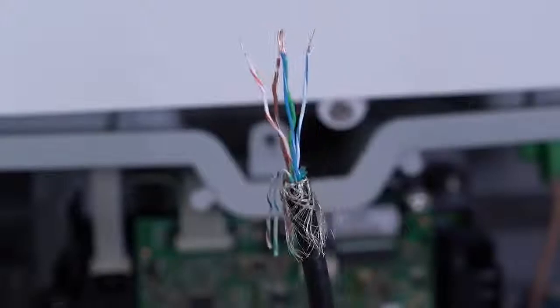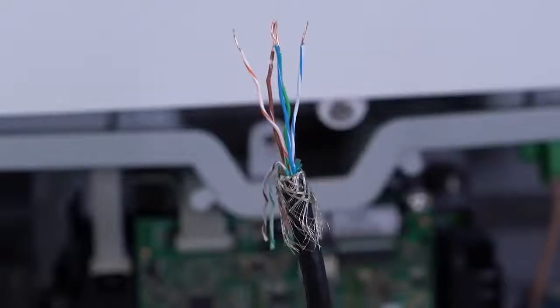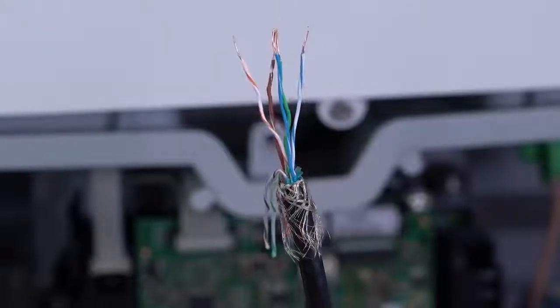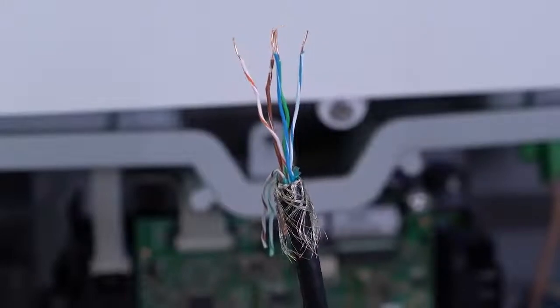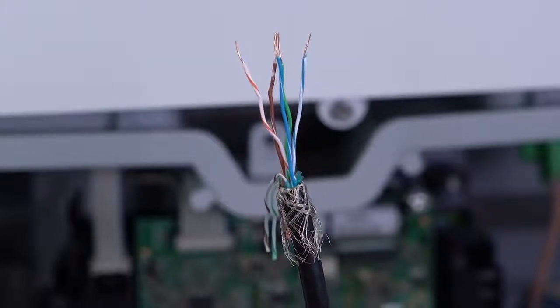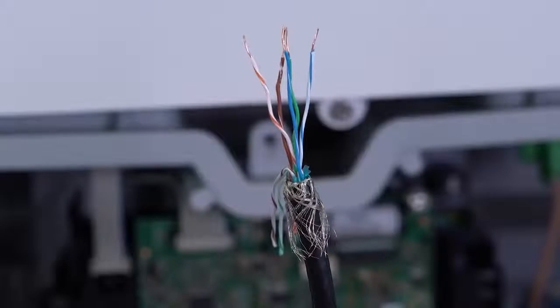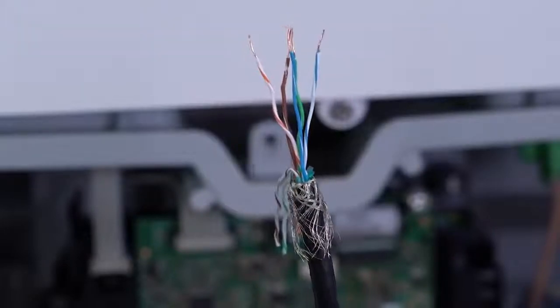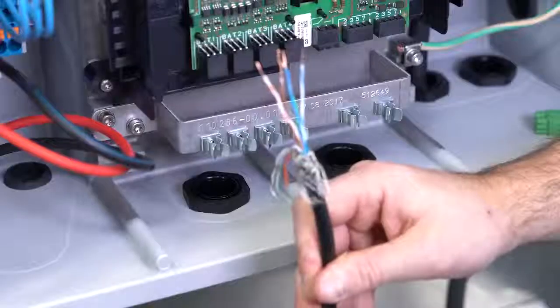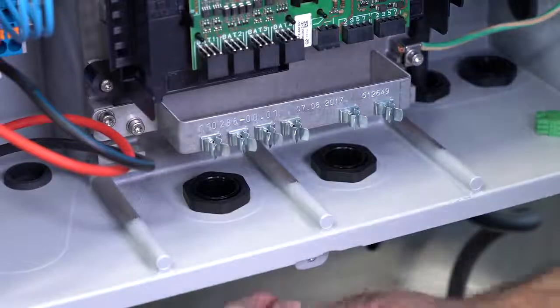All we need for the communication between the battery and the inverter itself is this CAN bus communication cable. Now, we have already stripped the endings of the CAN bus cable. Unless provided as part of the battery, SMA recommends using a cable such as a CAT 5E or similar. Note that the cable is not provided in the scope of the delivery. Next, I'll pass the cable through the intended cable gland.